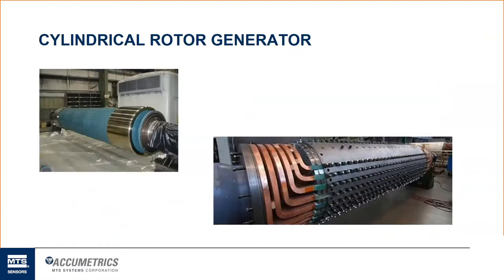So most gas and steam turbines use what's called a cylindrical rotor. You can see that here. These consist of this cylindrical style rotor. There's a bunch of forgings that are slotted to accommodate the turns of wire, which you can see in the copper conductors. They're about a 3 or 4 inch wide copper bus bar, copper conductor, that run down into these dovetail forging grooves and form a giant turn of wire, just like a motor or generator, same concept. There's many thousands of these turns of wire.